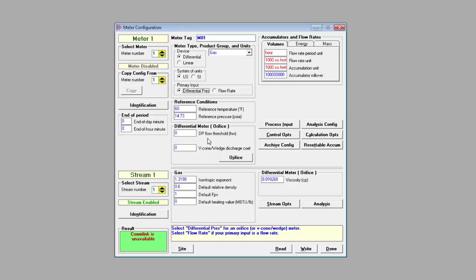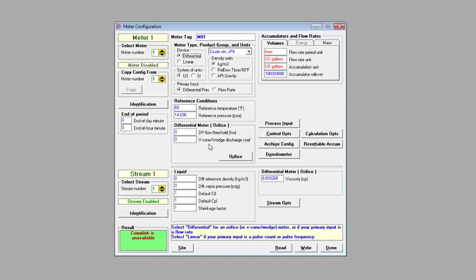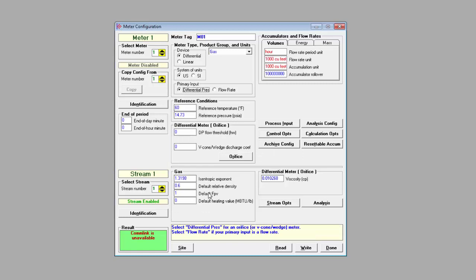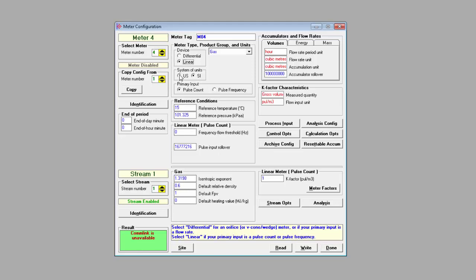The common parameters apply to all applications. So they don't change according to your selections up here and should be configured. They include reference temperature and reference pressure as well as the units to be used for accumulators and flow rates. The application specific parameters are those that are contingent on your selections up above. For instance, you could have the frequency flow threshold and pulse input rollover for a linear pulse count meter. Or you could see differential pressure threshold and V-cone wedge discharge coefficient for a differential pressure meter. If you set gas as the product group, you'll have the gas parameters to configure here or the liquid parameters if you chose liquid. If you chose a linear meter such as a turbine, you'll have the k-factor characteristics here where you can select the units for the k-factor.